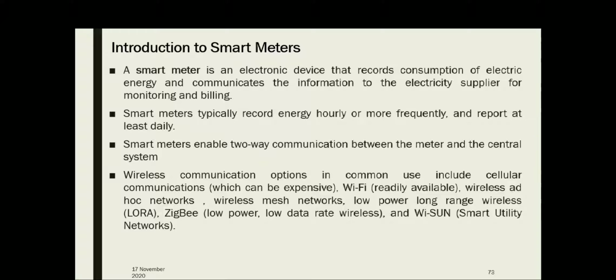A smart meter supports bidirectional communication. That is the important thing. That is a communication between the meter and the central system. Also, a smart meter has the built-in ability to disconnect or reconnect certain loads remotely and can be used to monitor and control the user's devices also, so that they can manage the demand and loads within the smart building.